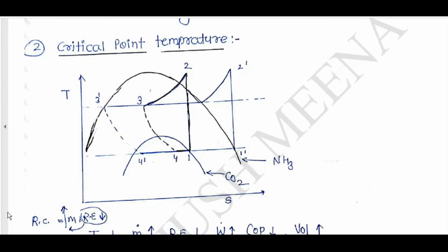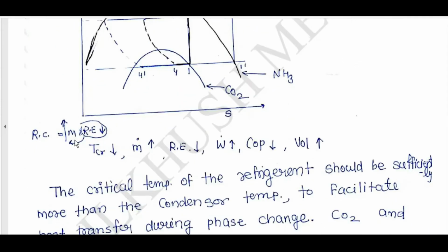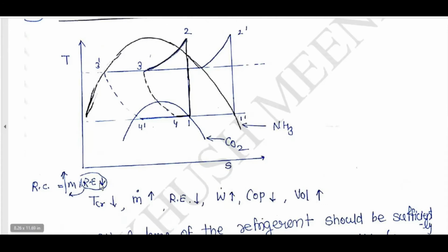Second parameter, critical point temperature. On the T-S diagram, for NH3 it is higher; for CO2 it will be lower, like this. RC is equal to m dot into RE. Refrigeration effect decreases, m dot increases. Refrigeration effect decreases, W dot increases, COP decreases.